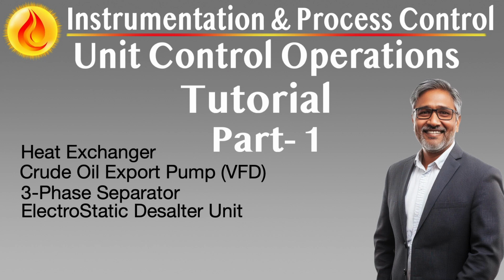transients. Wash water injection, critical for diluting and mobilizing salts, is no longer operated on fixed crude-to-water ratios. Instead, flow control is dynamically adjusted using conductivity meters on desalted crude and/or brine, inline salt analyzers, and process modeling. If downstream crude conductivity begins to drift above specification, the system can preemptively increase wash water or chemical dosage. Anti-surge control logic ensures that increased wash water does not overburden brine handling systems or destabilize the interface level.